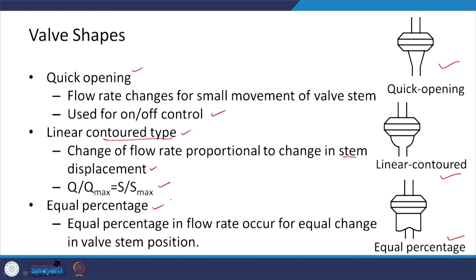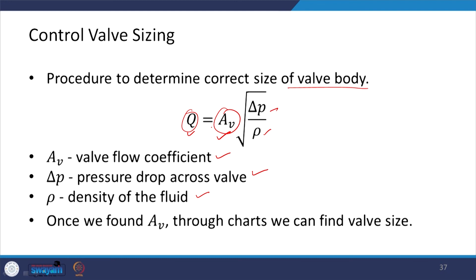Then we can also look at the control valve sizing. The procedure to determine the correct size of the valve body uses the relationship for discharge, that is Q = AV root of delta P by rho, where AV is the valve rate flow coefficient, delta P is the pressure drop across the valve, and rho is the density of the fluid. Okay. So, if I know the Q value and I know this value, I can find out AV, and if I know the AV, then I can use the chart to find out the size of the valve.